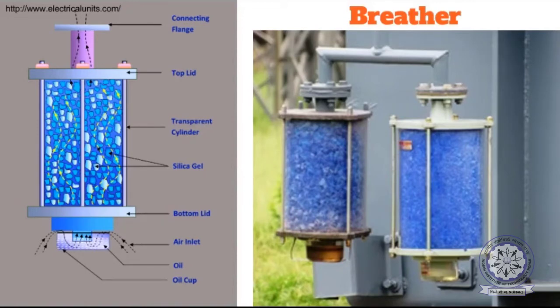But whenever it is under less load, it will be at a lower temperature. Oil will contract, and then air has to be sucked in. So during that time, the air enters through this silica gel breather. So here you can see the silica gel crystals. Are you aware of silica gel crystals? Yes, sir.